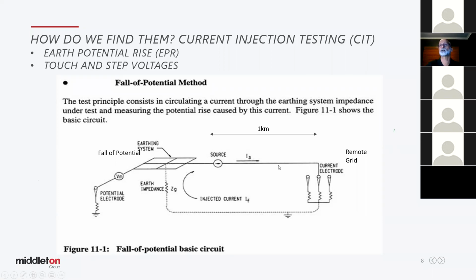Now, to help us do that, we run a temporary remote lead out, let's say, 1 kilometre into the field, and we just build a little temporary grid there with some stainless steel stakes in the ground, and that just allows us to get some good contact with the ground and push our test current around here. If we push 50 hertz, it'll just disappear. Our little signal will disappear into the fundamental. So we normally do, or we always do, off-frequency injection testing. So 56 hertz is a common one that we can use. This way, with our frequency tuned voltmeters, we can measure the voltage on fences and of the soil.